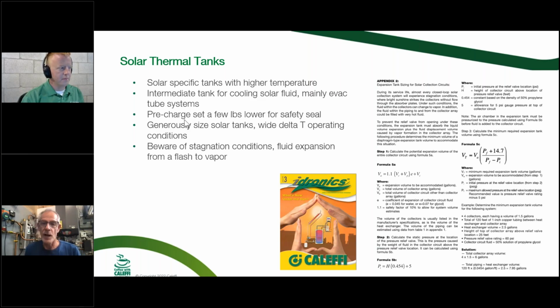And where it gets even a little bit more complicated when you start sizing, which is why the formula gets kind of big over there on the right for solar thermal, is to think about a solar thermal system when it goes in a stagnation condition. And what I mean by that is the pump goes off for whatever reason. Maybe the tank got up to temperature, maybe the controller failed, the pump jammed up, whatever. And now you've got a collector up there going well over 300 degrees. I think we calculated on a flat plate collector somewhere around a 344-degree stagnation temperature on a full sun day. What's important to know there is that temperature is probably only going to be seen at the collector and some of the piping. So I don't want to size my expansion tank to handle from 0 degrees to 344 degrees. So what this formula will allow you to do is subtract out the volume of the fluid that's in the collector and in the piping that could be exposed to that temperature, and back that out of the formula so I don't have to try and accommodate a 344-degree temperature differential, essentially from a wintertime 0-degree temperature at a collector to a stagnation temperature condition up there.